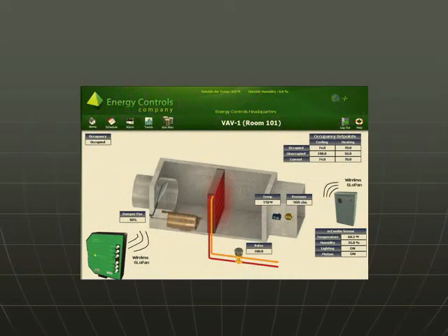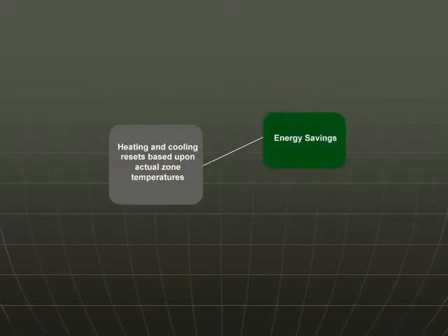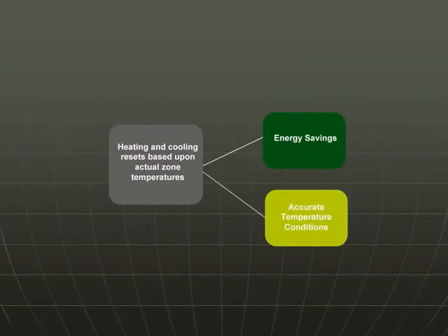Using information from the zones, the controllers calculate the required set points and, depending on demand, switch on the respective heating and cooling sources. This makes certain that aggregates or pumps do not constantly operate, thus minimizing the number of operating hours. Heating and cooling resets based on actual zone temperatures not only fine-tune your energy savings, but also support accurate temperature conditions within the zone-controlled environment.